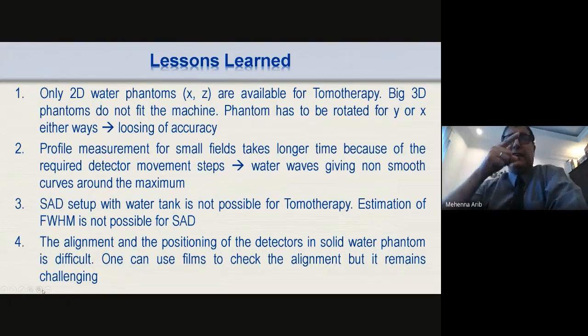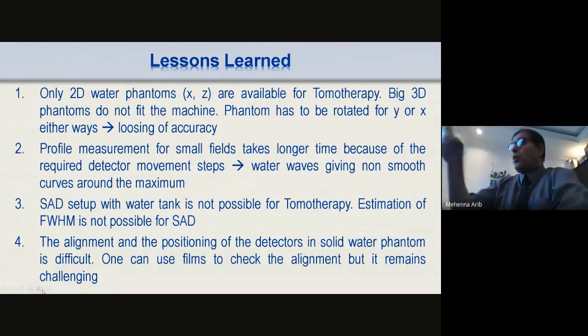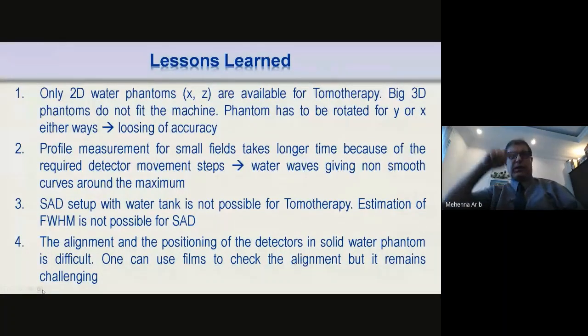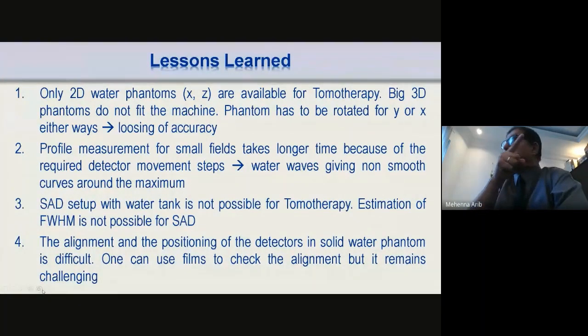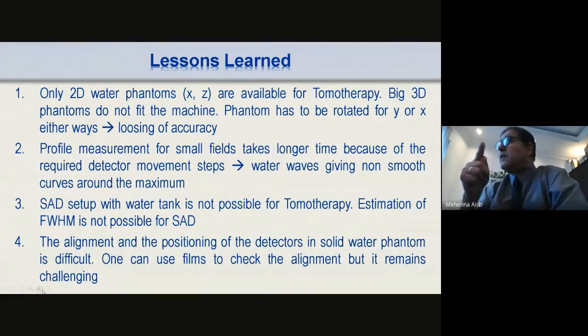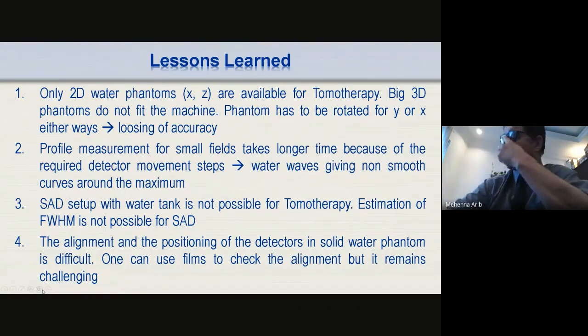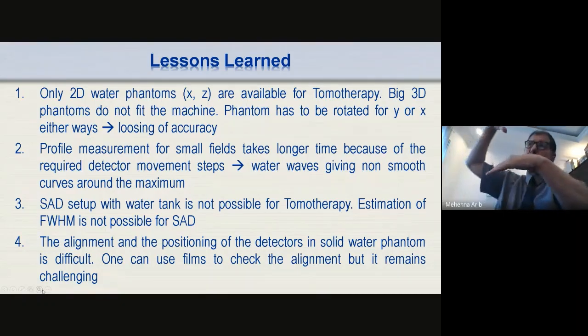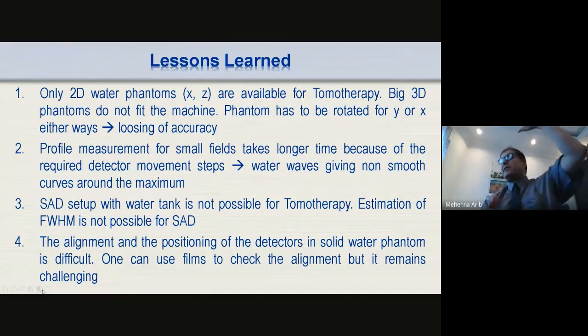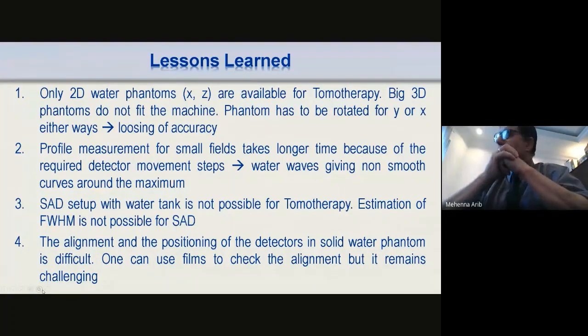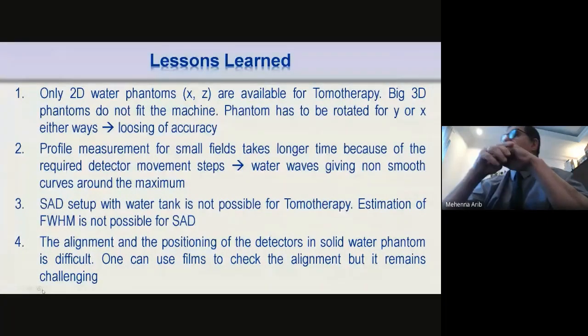If you scan the small fields too fast, the water waves will completely disturb your beam profile, and you get strange profiles. So you need to scan smoothly, down to 0.1 millimeter per second if possible. Very small movement. Okay. The SAD setup with a water tank is not possible for tomotherapy, because of the distance of the gantry, if you try to get the SAD, you will not get it. So we were not able to make the SAD configuration for the tomotherapy.